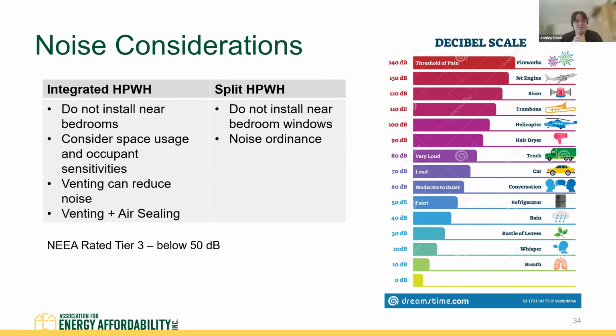And then something else to think about, especially if you're installing these inside, is noise consideration. So with tank type heat pump water heaters, if they're inside, you want to make sure they're not too close to bedrooms, and you want to consider space usage, occupant sensitivities to noise. There are ways that you can vent or air seal closets to also help mitigate noise further. If you're installing one of those split heat pump water heaters where the compressor is outside, that can help with noise, because then you've just completely removed the compressor from the interior at all. But you want to make sure they aren't too close to bedroom windows or too close to adjacent properties, and make sure they're meeting the noise ordinances of your AHJ.